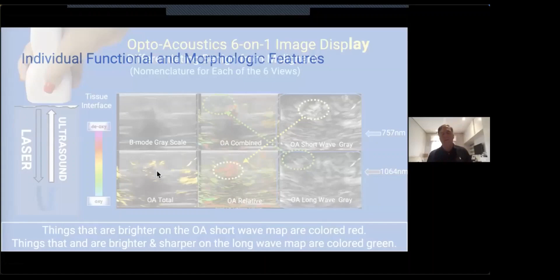So what are the individual functional morphologic features we can see? Well, we can see the total amount of hemoglobin. If I go back to this previous image, the yellow map is total hemoglobin. So it's not telling you what's oxygenated or deoxygenated. It's adding the oxygenated and deoxygenated together, and it's giving you a total hemoglobin map. The OA relative is the most sensitive map, but it gives you more background signal. The OA combined is cleaner, better for downgrading benign masses, but it's filtered a little bit, so it's a little less sensitive. So there are various uses for each.